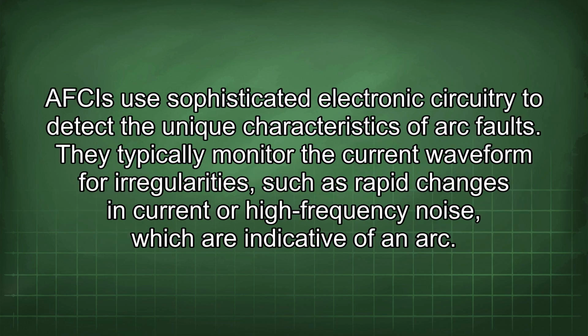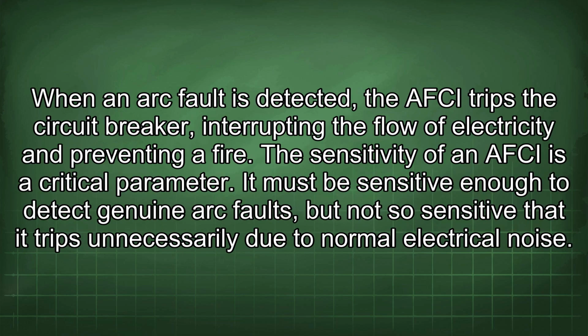AFCIs use sophisticated electronic circuitry to detect the unique characteristics of arc faults. They typically monitor the current waveform for irregularities, such as rapid changes in current or high-frequency noise, which are indicative of an arc. When an arc fault is detected, the AFCI trips the circuit breaker, interrupting the flow of electricity and preventing a fire. The sensitivity of an AFCI is a critical parameter.